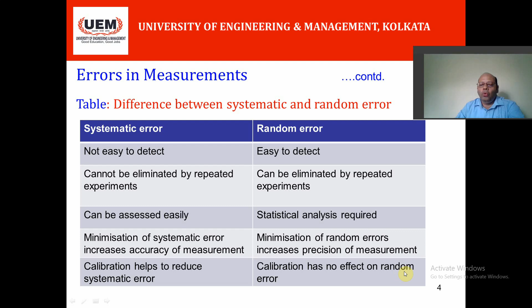This is a very important thing: the minimization of systematic error increases the accuracy of the measurement, and minimization of random error increases the precision of measurement. I have already discussed that calibration of the instrument helps to reduce the systematic error, whereas calibration has no effect on the random error. So to get this idea between random error and systematic error properly, I have used another chart where it shows the difference between systematic and random error.